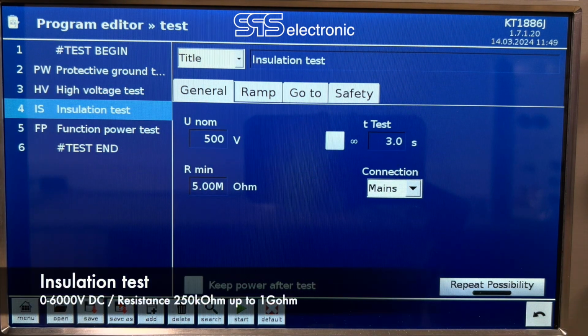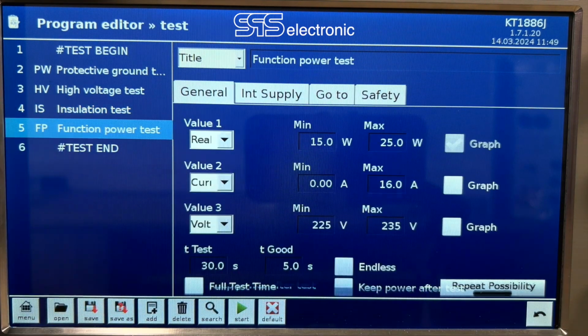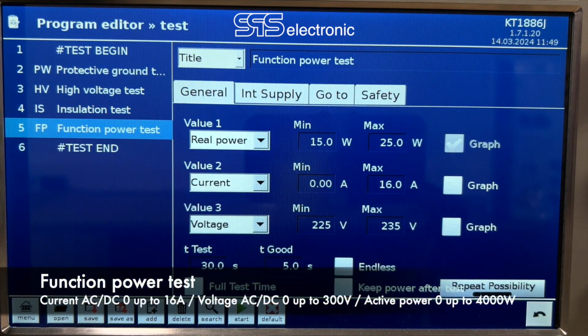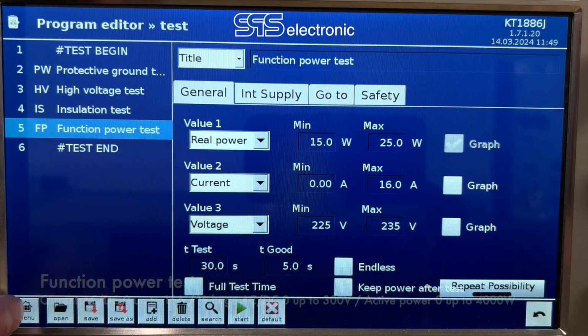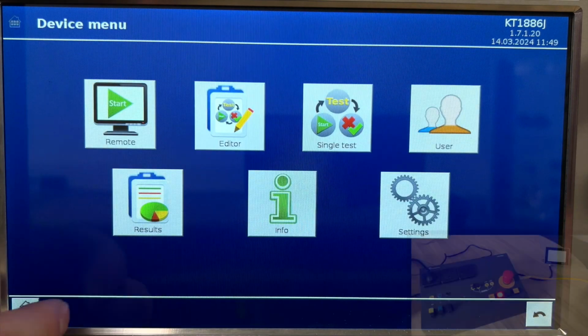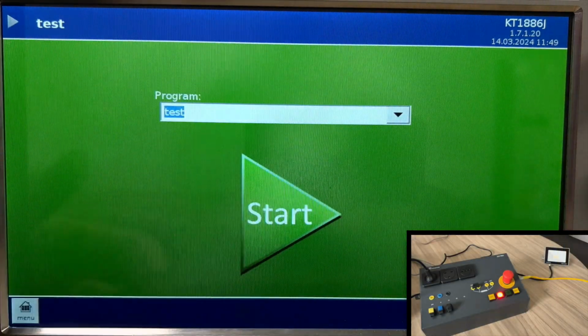The third one is insulation test, where we will set up voltage and minimum resistance. Last step is function power test, where you can measure 3 values at once, which 2 of them will appear in graph. I choose real power, which should be around 20 watts, current, and input voltage. When we have all set up, we will go to main screen and start the test.